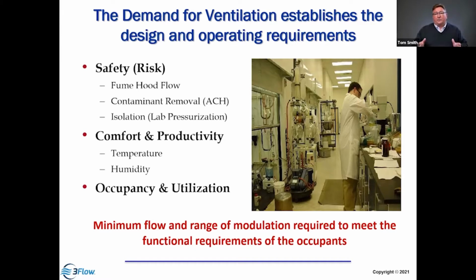So overall, when we're looking at total flow, we want to find what is that minimum flow that's necessary to meet the needs of the occupants, and then that range of modulation that's required to get from minimum to maximum flow. And that definition is going to apply not only to the fume hood from sash closed to sash open, but also to the laboratory from minimum to maximum flow. So we need to know that minimum flow and the range of modulation.